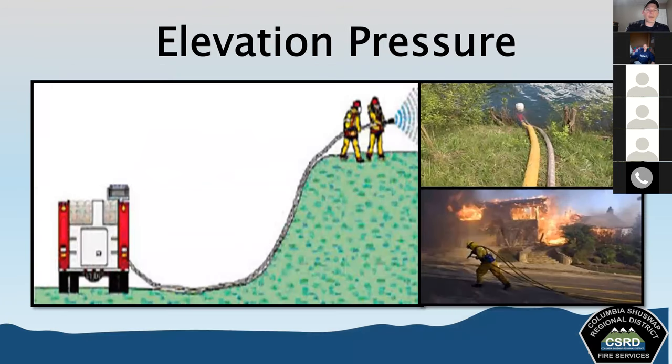So what Annette was talking about there with bringing elevation into it is elevation pressure. Static pressure is generally created by elevation pressure, pump pressure, or both. Elevated water tanks supply pressure to municipal water systems because of the difference in height between the water in the tank and the underground delivery. So the gravity itself is actually creating pressure from that elevation, right?